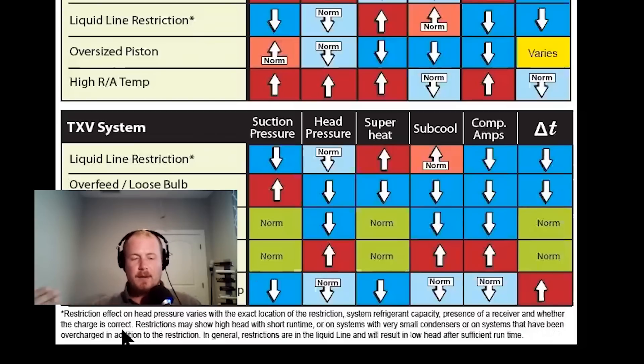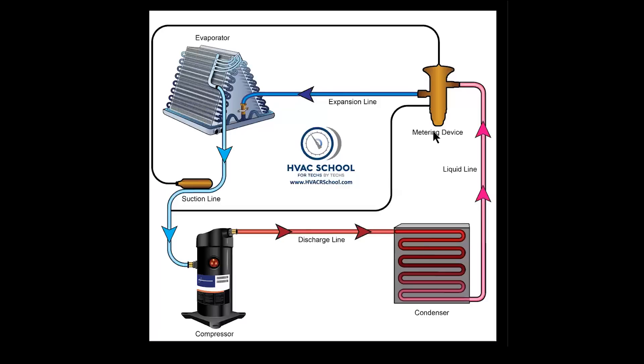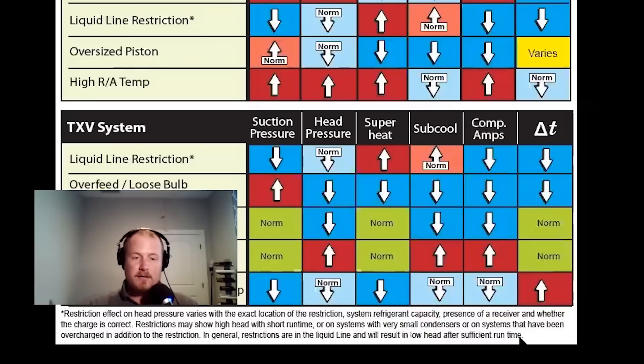In a lot of cases you'll have a restriction coupled with an overcharge. Say you have a restricted liquid line dryer — the technician shows up, sees that head pressure and suction pressure are both low, and concludes he's low on charge, so he starts adding refrigerant. Eventually head pressure will go up because as you fill the condenser more and more, the volume decreases to the point of hydrostatic pressure buildup — you get hydrolocked because you have so much liquid inside the condenser, which can cause some really high pressures. That's a real problem.